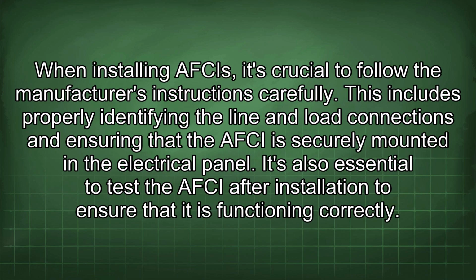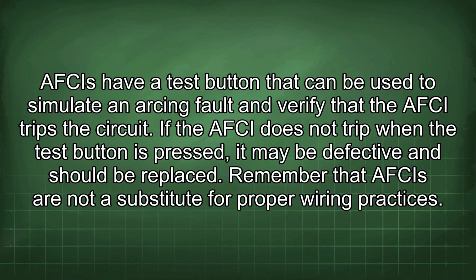When installing AFCIs, it's crucial to follow the manufacturer's instructions carefully. This includes properly identifying the line and load connections and ensuring that the AFCI is securely mounted in the electrical panel. It's also essential to test the AFCI after installation to ensure that it is functioning correctly. AFCIs have a test button that can be used to simulate an arcing fault and verify that the AFCI trips the circuit. If the AFCI does not trip when the test button is pressed, it may be defective and should be replaced. Remember that AFCIs are not a substitute for proper wiring practices.